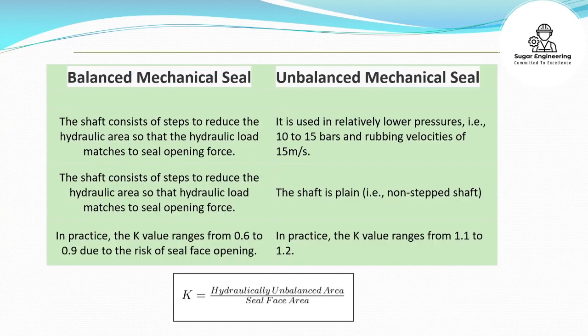Balanced mechanical seal: The shaft consists of steps to reduce the hydraulic area so that the hydraulic load matches the seal opening force. In practice, the K value ranges from 0.6 to 0.9 due to the risk of seal face opening. Unbalanced mechanical seal: It is used in relatively lower pressures, i.e., 10 to 15 bars, and rubbing velocities of 15 meters per second. The shaft is plain, i.e., a non-stepped shaft. In practice, the K value ranges from 1.1 to 1.2.